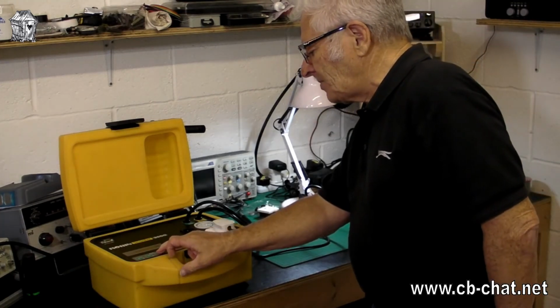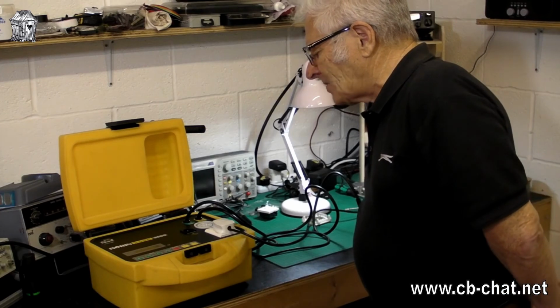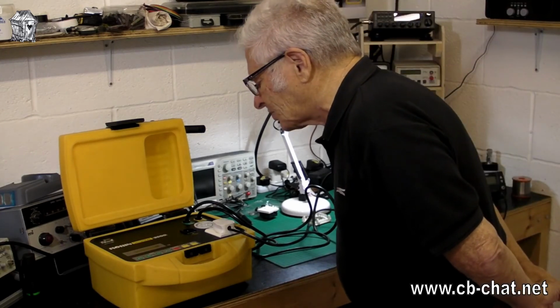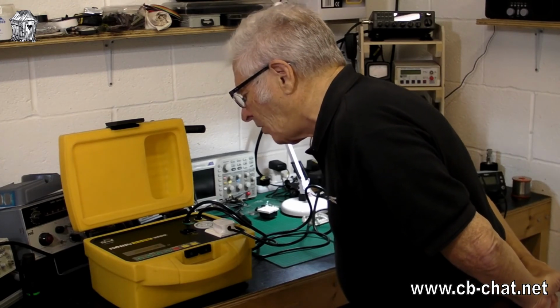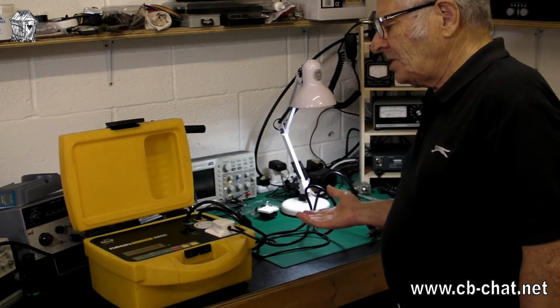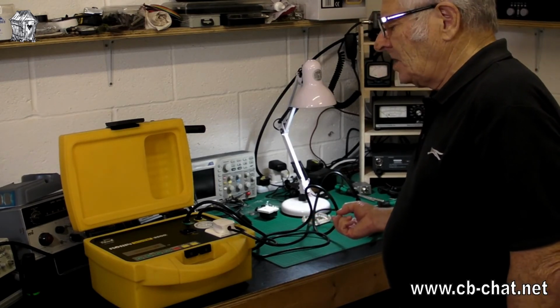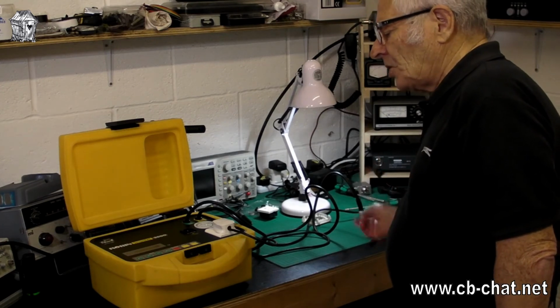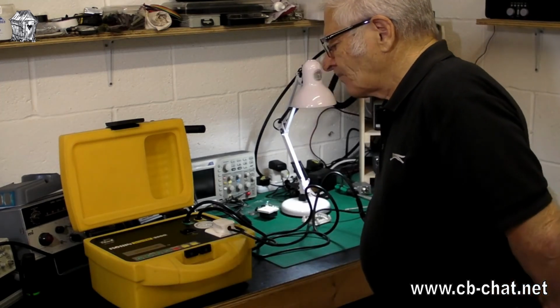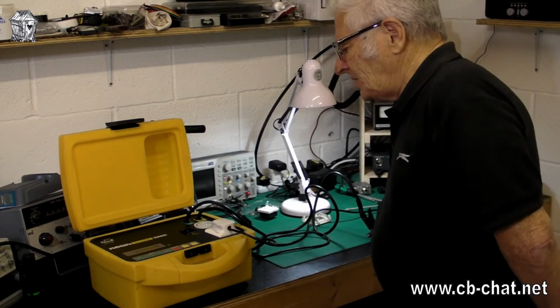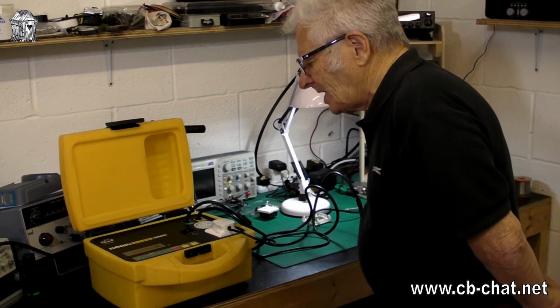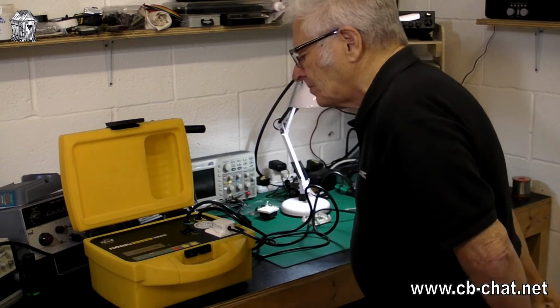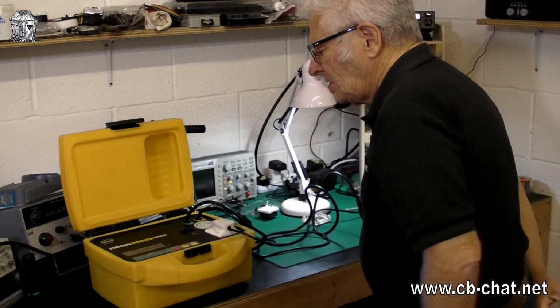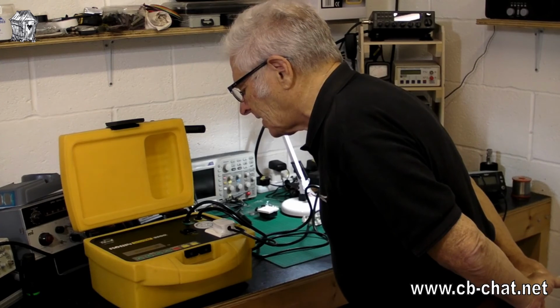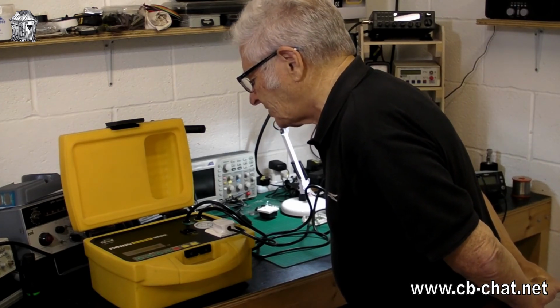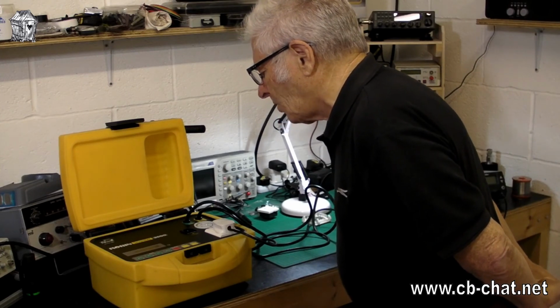But we can do this at various currents. See, if we press this one, we can bang 5 amps down it, and we put 5 amps down it. Again, it's going down the earth lead, and it says 0.12 of an ohm. So we know it's safe then. If something goes wrong and it has an electrical fault, it's going to short out to ground. We can put 8 amps through it. I can do this. You wouldn't put these high currents through delicate equipment. There we are. 0.1 of an ohm. We can even go crazy and put 25 amps. Here we go. 26 amps it says, is it? Yeah. Testing 26 amps. Result 0.09 of an ohm.